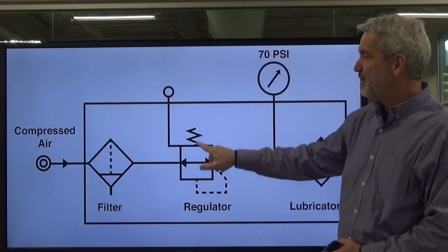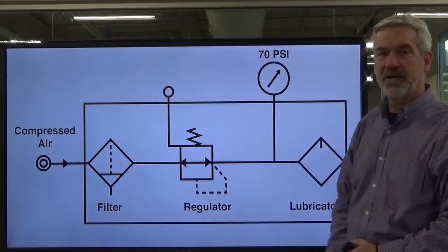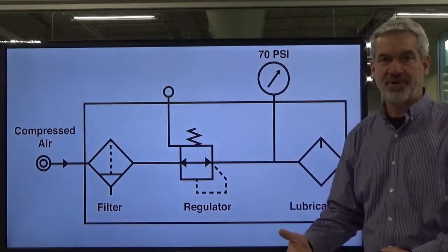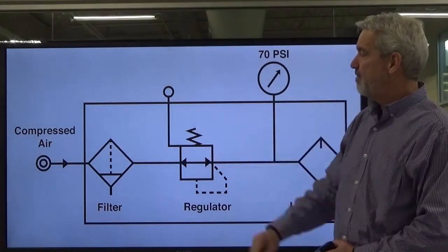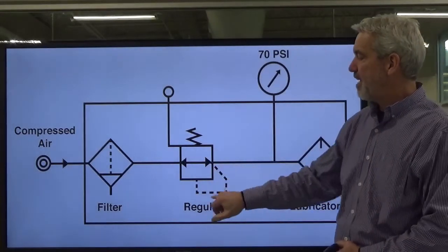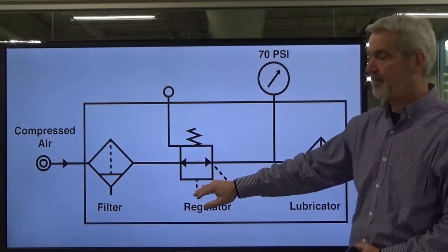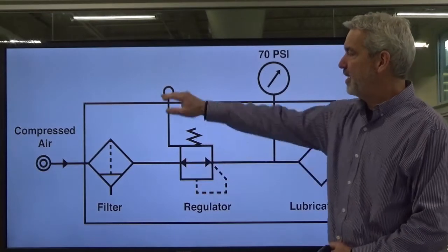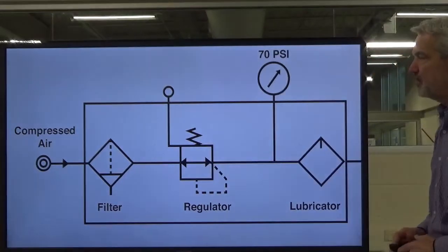We are using the pilot pressure, but you'll notice there's no arrow going through here at a slant that tells us it's variable or adjustable. So this is a fixed value, and whenever the pilot pressure hits that fixed value, it will lift it up there and dump it in the atmosphere. But some more symbols for you.